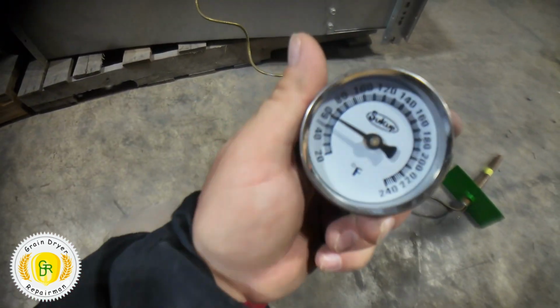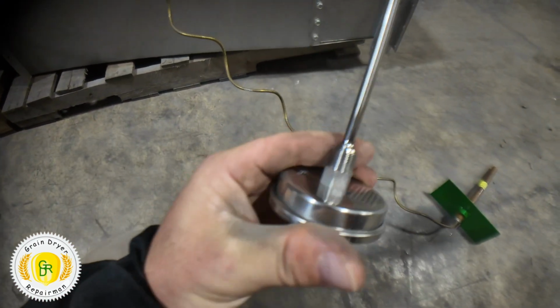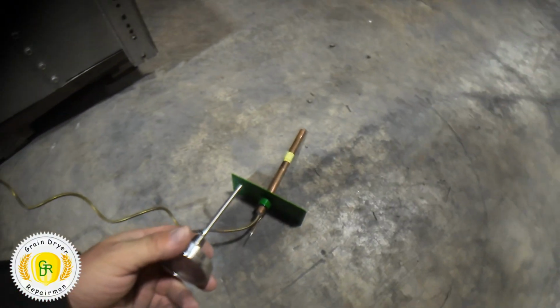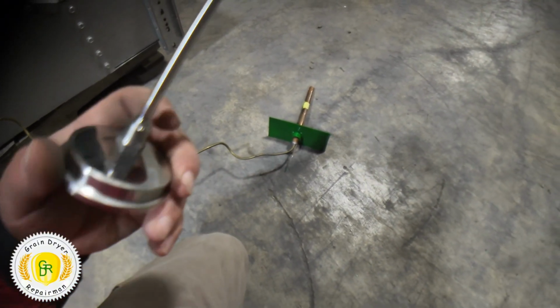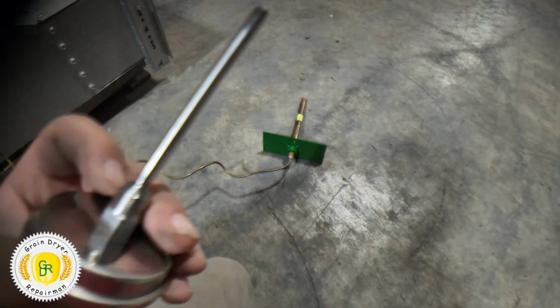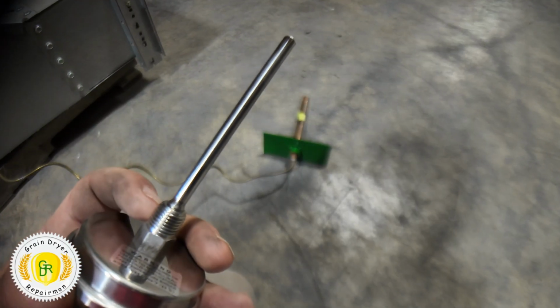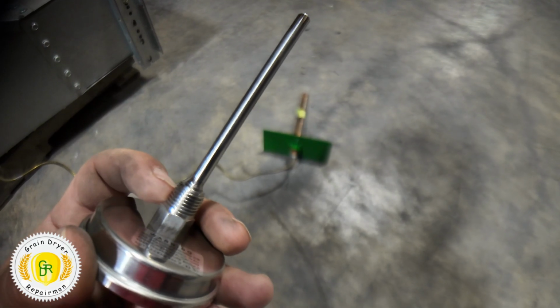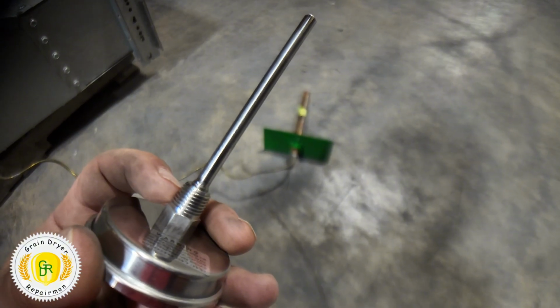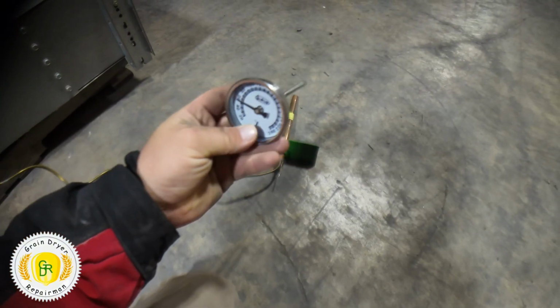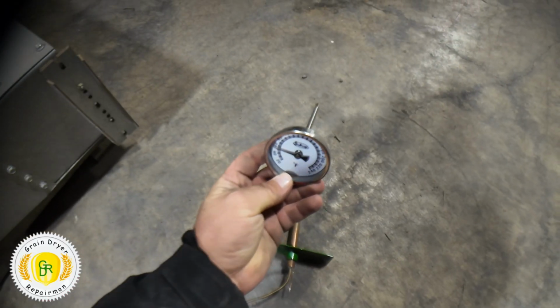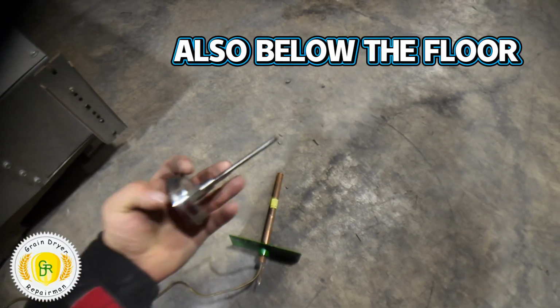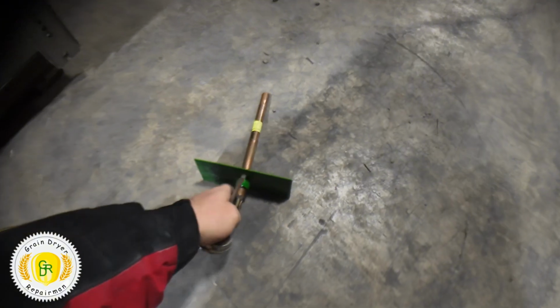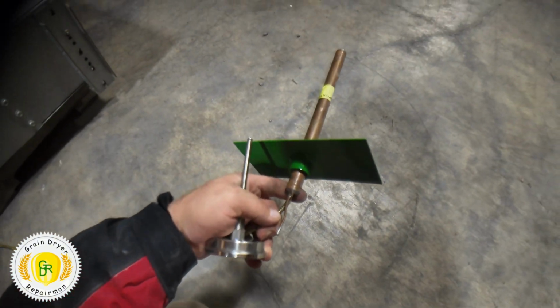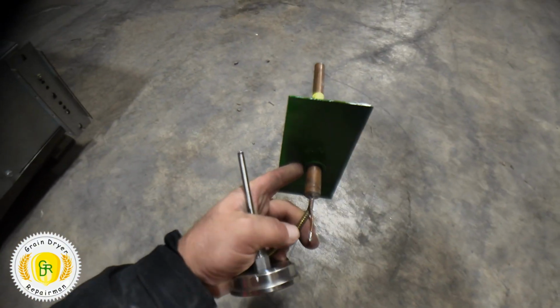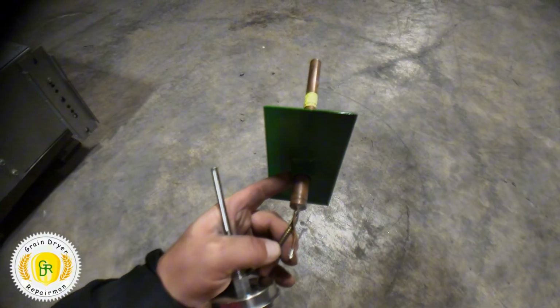This temperature gauge, you go within 12 inches of your temperature probe and you drill a 1/2 inch hole. If you drill an exact 1/2 inch hole, this pipe thread will thread directly into that, right into the sidewall. The temperature gauge must be installed within 12 inches of the temperature probe. That plate needs to be installed to hold the temperature probe straight.